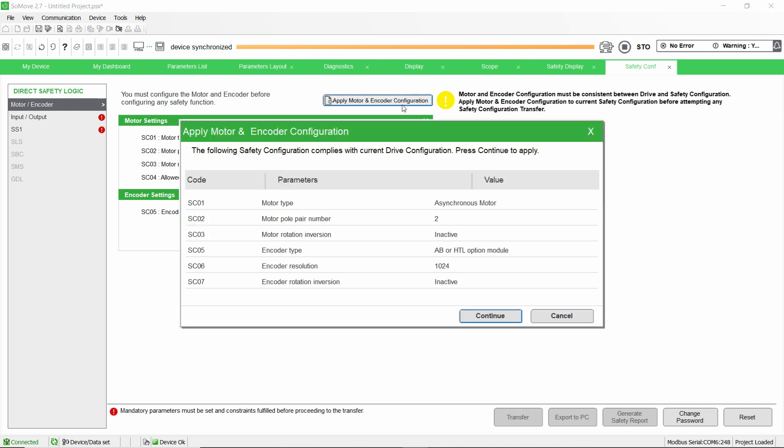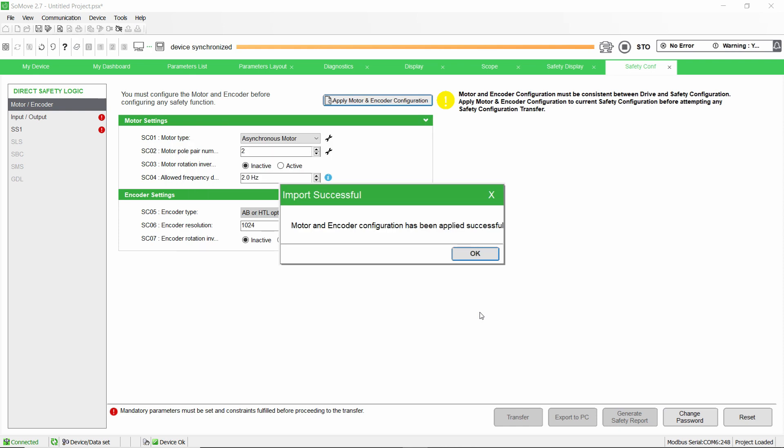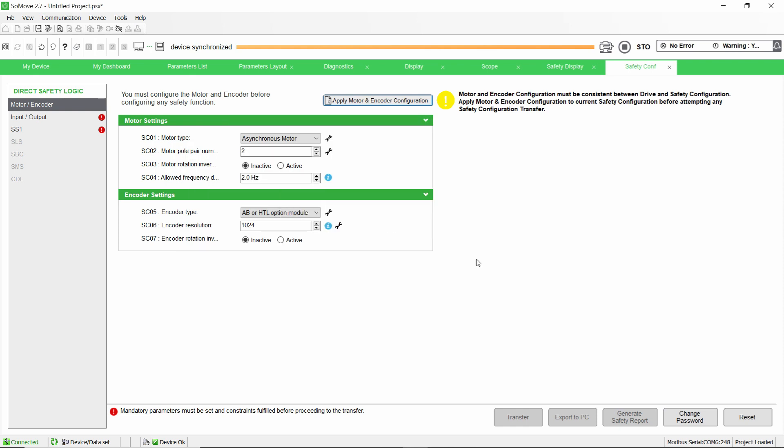You are now in the Motor/Encoder menu. The first step of the safety configuration is to configure the motor and encoder parameters. These parameters must be consistent with the standard parameters of the drive defined earlier. You can enter the value manually or you can click on the Apply Motor and Encoder Configuration button.